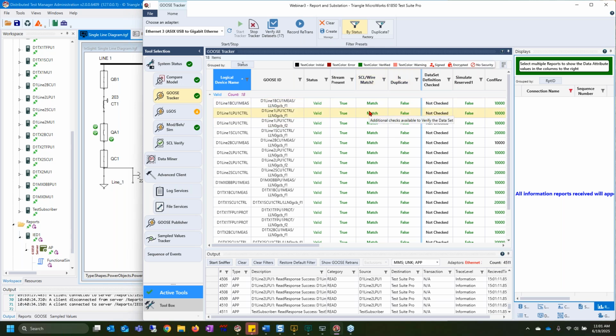The alternative is if a stream is missing. So you tell TSP, I think there should be 18 GOOSE streams on the network, and you're only seeing 16. Well, that could be an indicator of you forgot to plug in your devices, or turn on your test sets, or plug in the device that's actually doing the goosing. So this is just a good, very quick sanity check to make sure all the streams of GOOSE that you're expecting are out there.